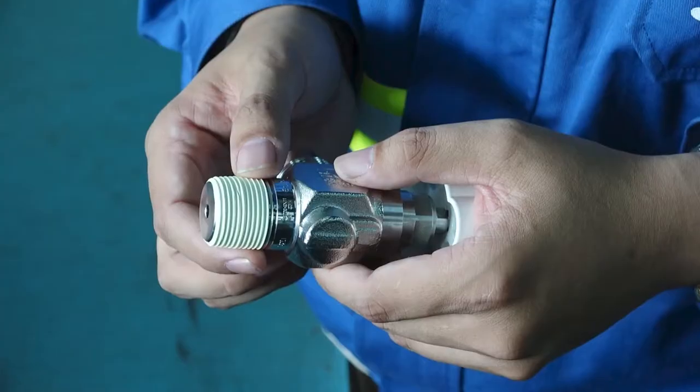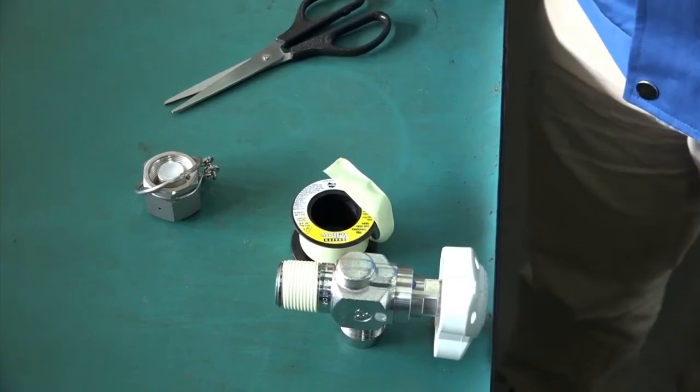Do not touch the tape with bare hands. Do not cover the end thread by tape. Do not expose more than one turn of thread at the small end.